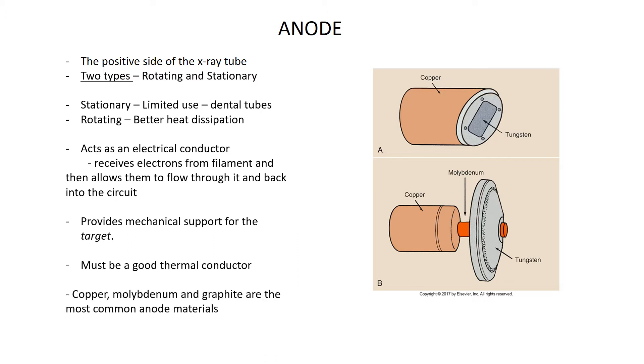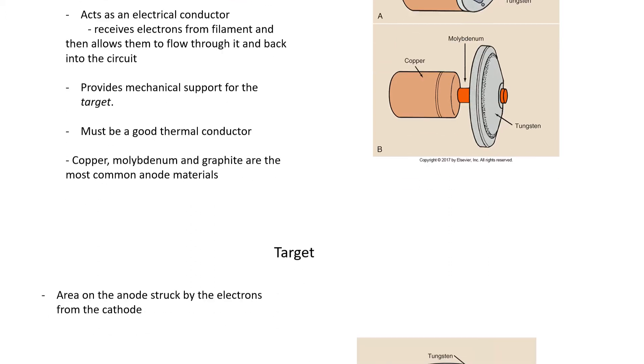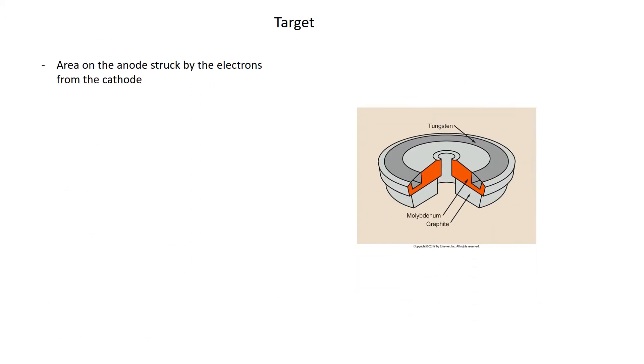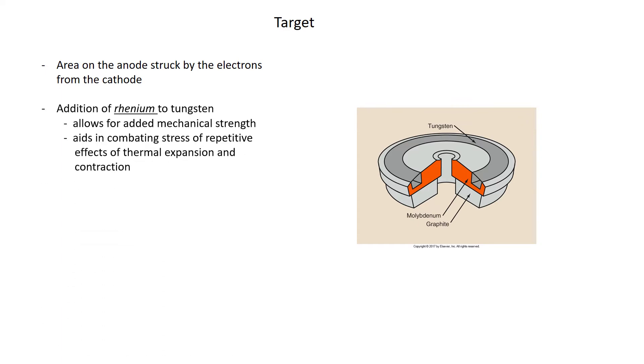As for the anode disc itself, copper, molybdenum, and graphite are the most common anode materials. Looking at the cross-section of the anode disc, we can see the graphite and the molybdenum. On the front of the anode disc is the target material where the x-rays are actually created — and that is tungsten. Rhenium is added to the tungsten, providing added mechanical strength and aiding in combating the stress of repetitive thermal expansion and contraction of the disc.